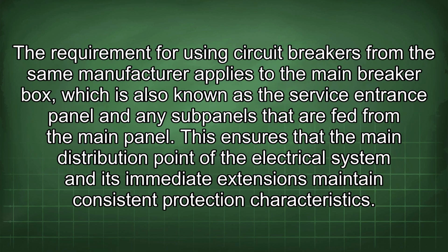The requirement for using circuit breakers from the same manufacturer applies to the main breaker box, which is also known as the service entrance panel, and any subpanels that are fed from the main panel. This ensures that the main distribution point of the electrical system and its immediate extensions maintain consistent protection characteristics.